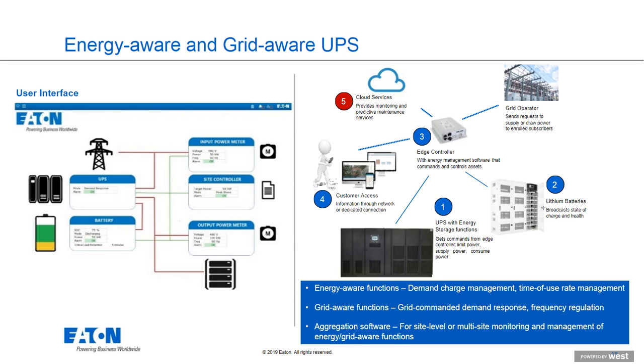Before, the input power was a little over 200 kilowatts. Let's say I set the target for 150 kilowatts—so I'm reducing demand on the grid by about 50 kW. Where does that come from? Look at the battery. It supplies that power temporarily, and once the need to reduce demand decreases, we stop discharging. Do we start recharging immediately like typical? Maybe, but we may defer charging until 1 a.m. when power cost is least expensive. So there's a lot of flexibility in how the UPS's capacity in kilowatts and the energy available in the battery can be used.